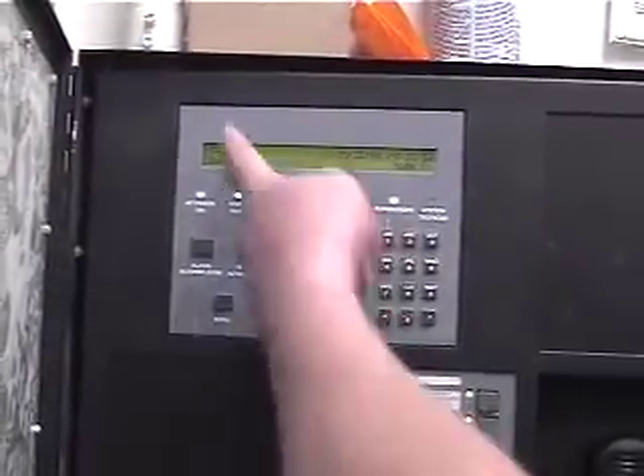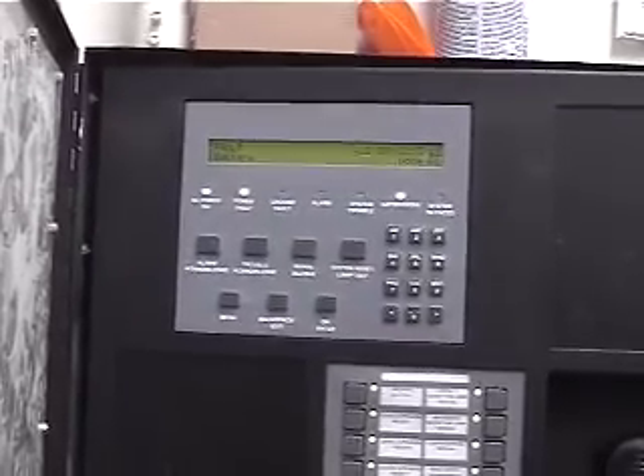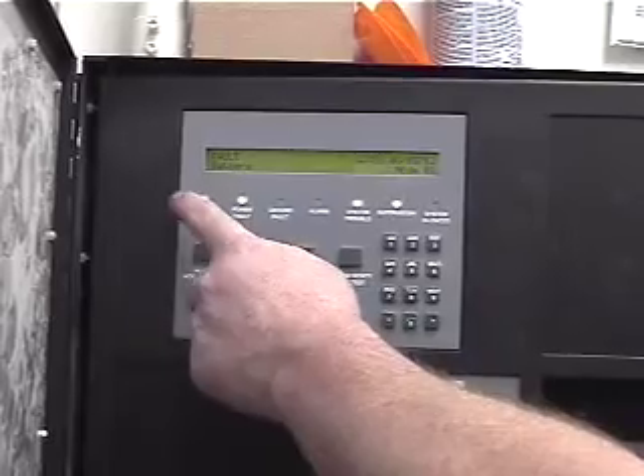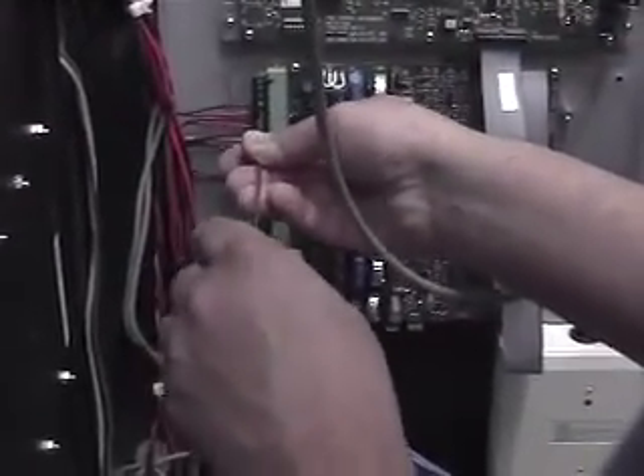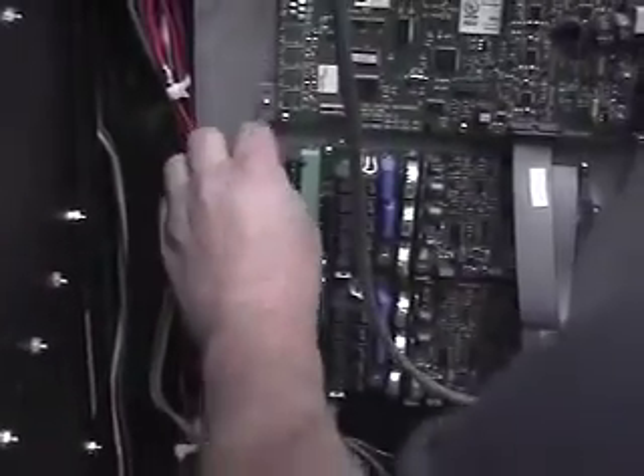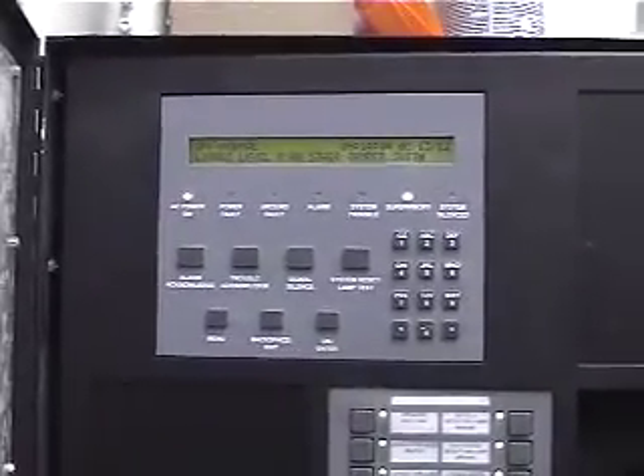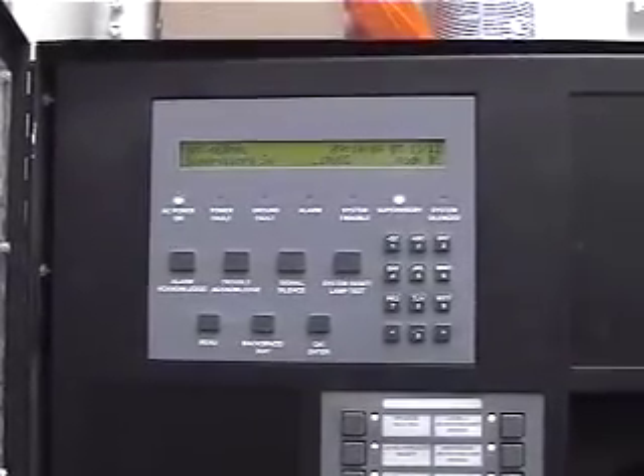We can unplug those and we can show you on that one when that goes to fault. So it comes up fault battery and then your power fault light comes on. And when you lose AC, this light will go off and your power light will come on also, and then it'll tell you AC fault. The amps in your speaker circuits, when you have one go into fault, this is amp one, this is amp two, it'll come up and tell you which node, which amp, and then which circuit on the amp goes into fault.